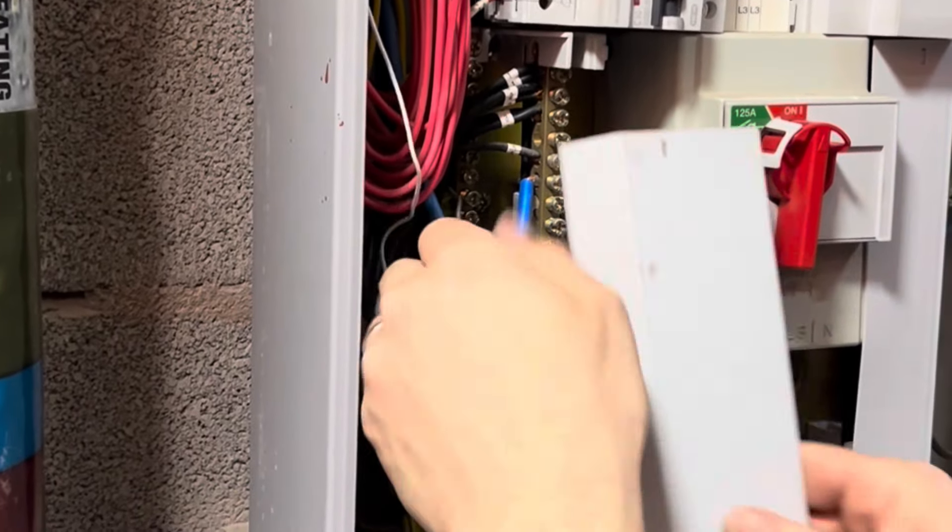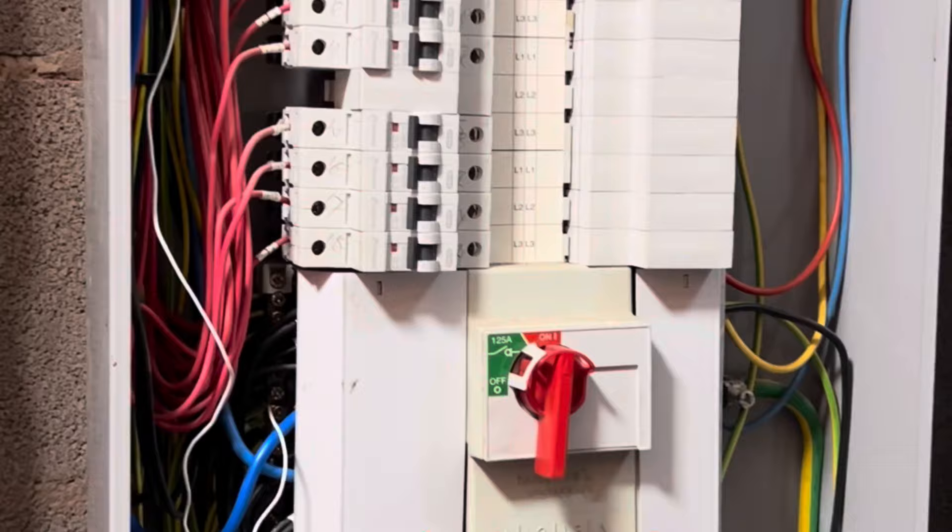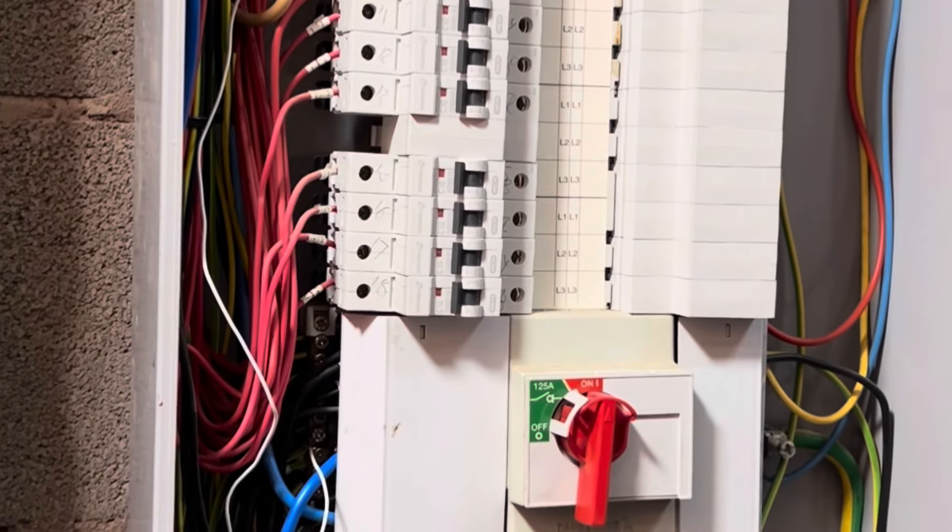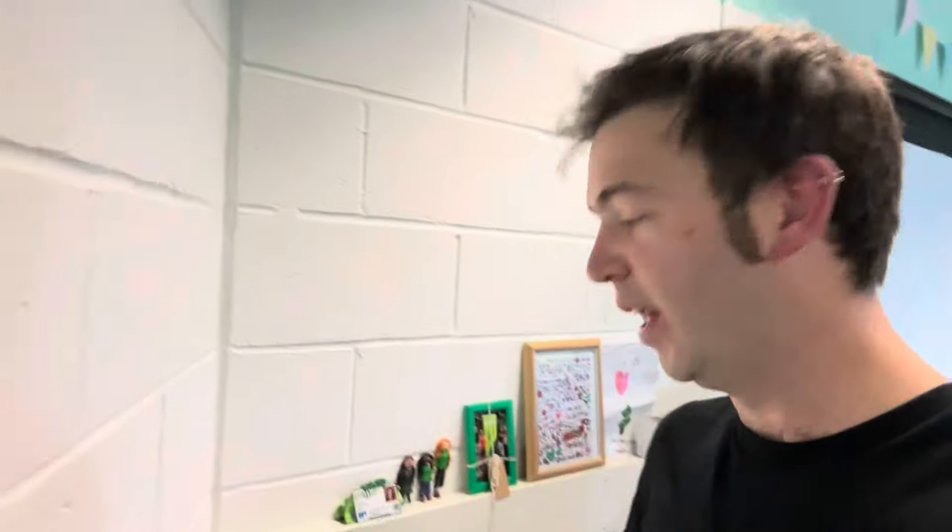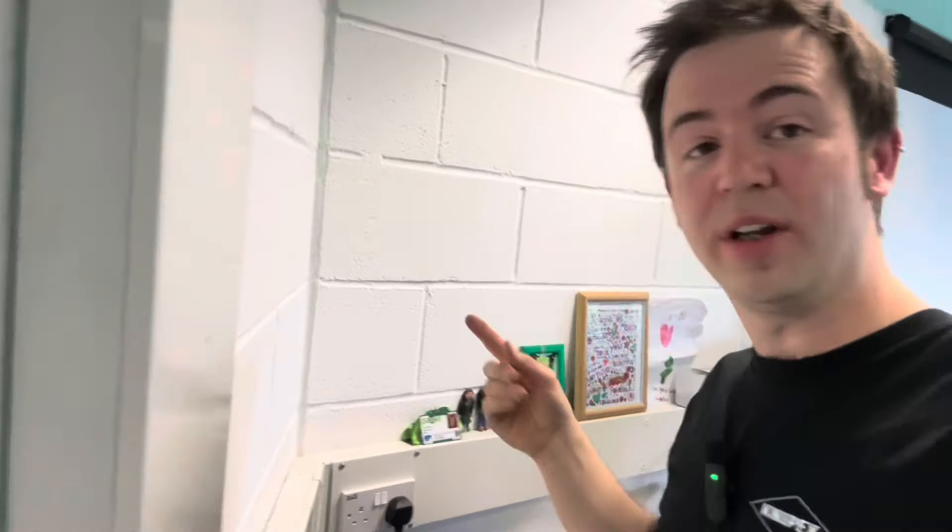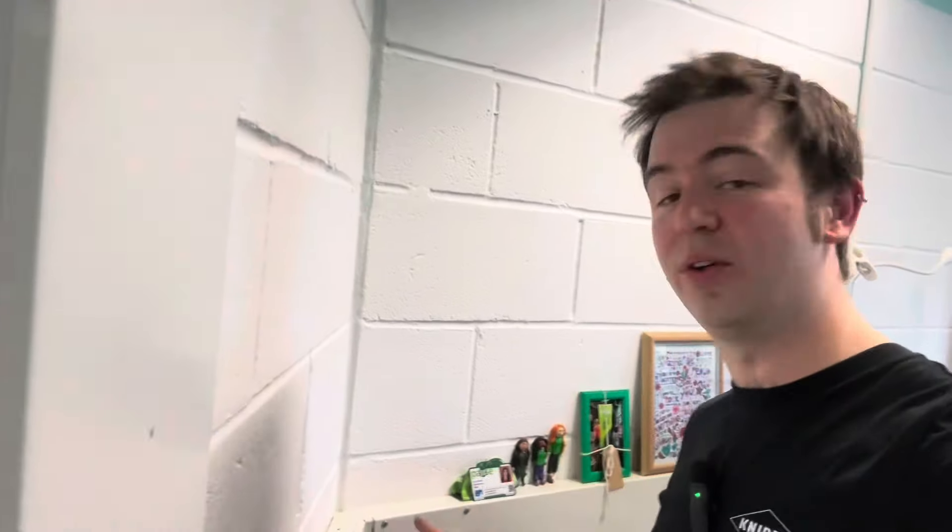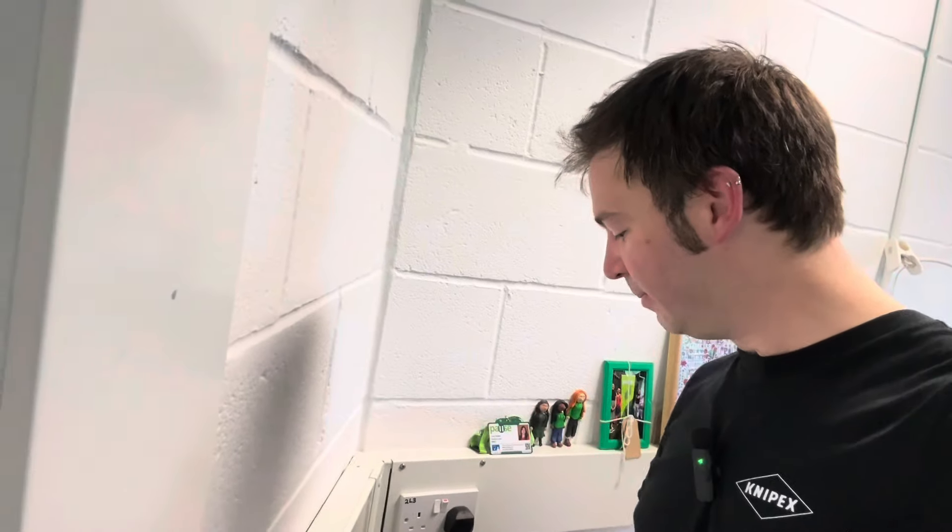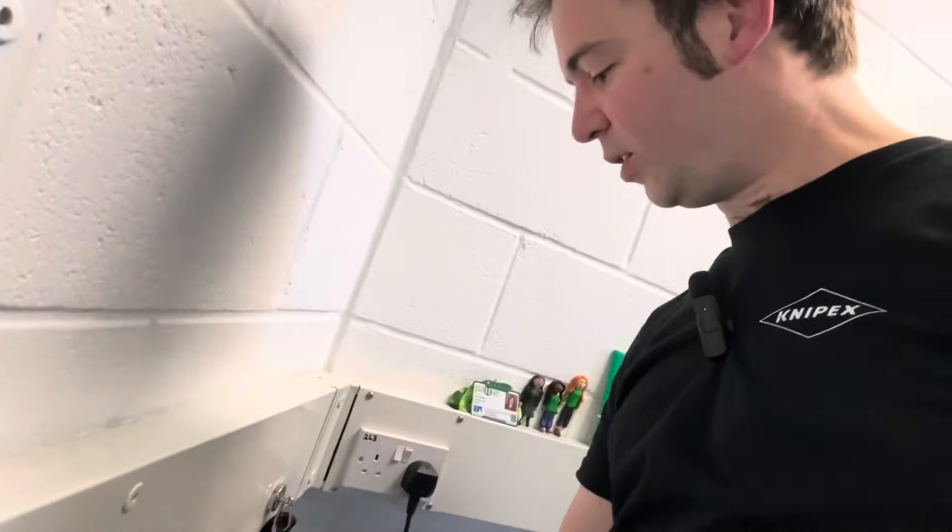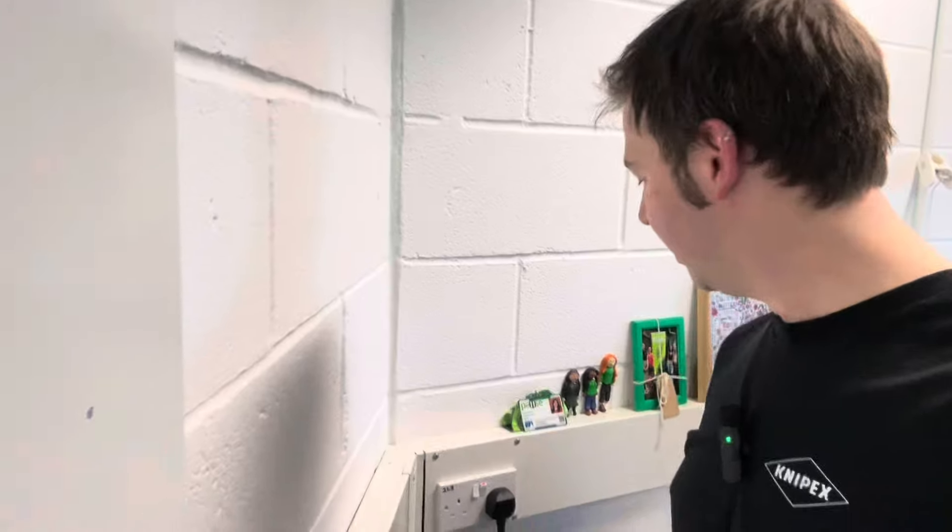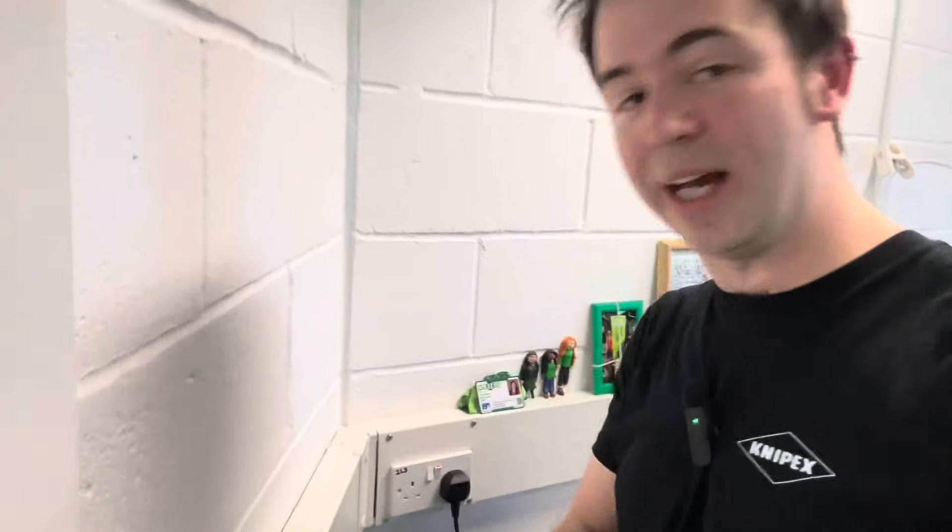All right, neutral cover back on. Now we'll give it a test. My colleague's just going to re-energize the circuit. You saw me just fit the pod, so I put the pod in, cover back on. He's now at the board. Like I told you in the video, you've got to do it from the load, so I'm just going to do a quick loop test and I'm going to do an RCD test and see what we get.